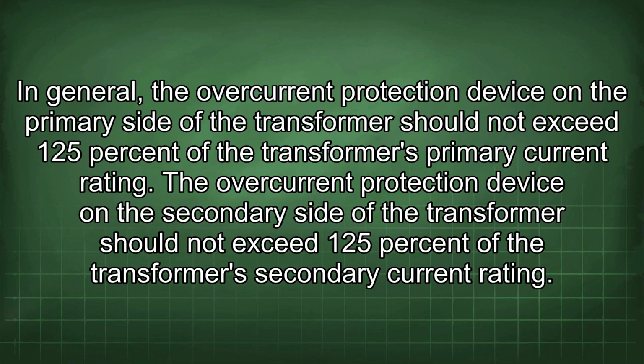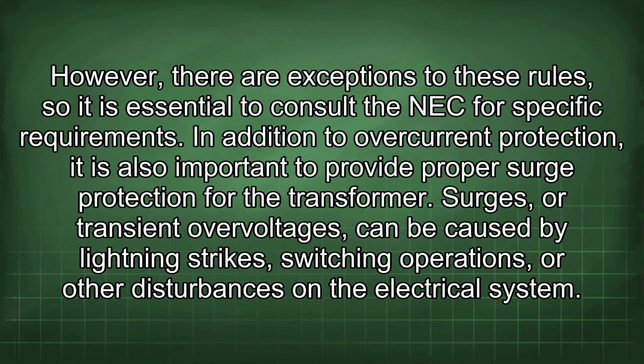In general, the overcurrent protection device on the primary side of the transformer should not exceed 125% of the transformer's primary current rating. The overcurrent protection device on the secondary side of the transformer should not exceed 125% of the transformer's secondary current rating. However, there are exceptions to these rules, so it is essential to consult the NEC for specific requirements. In addition to overcurrent protection, it is also important to provide proper surge protection for the transformer.